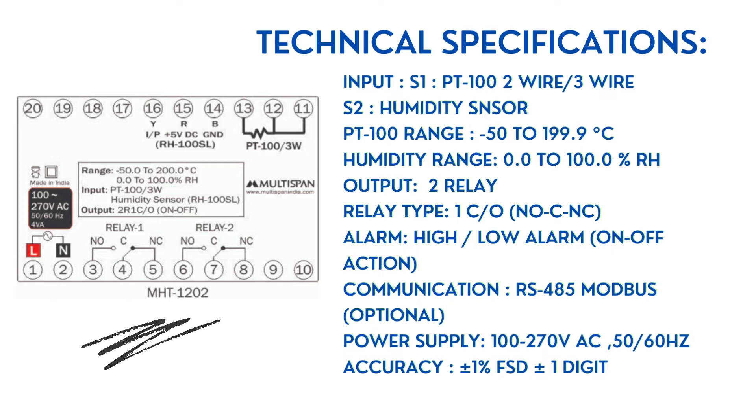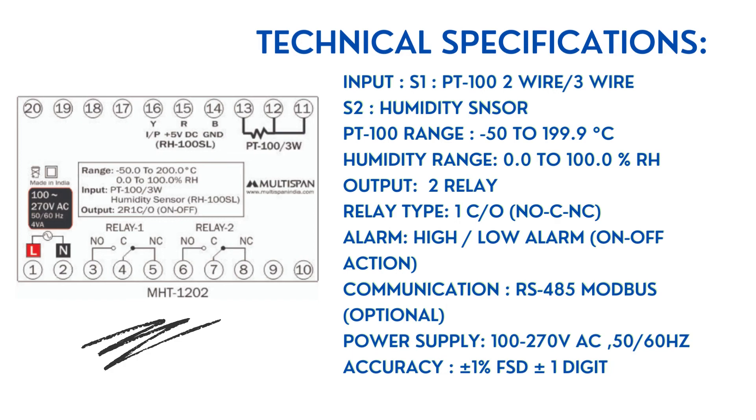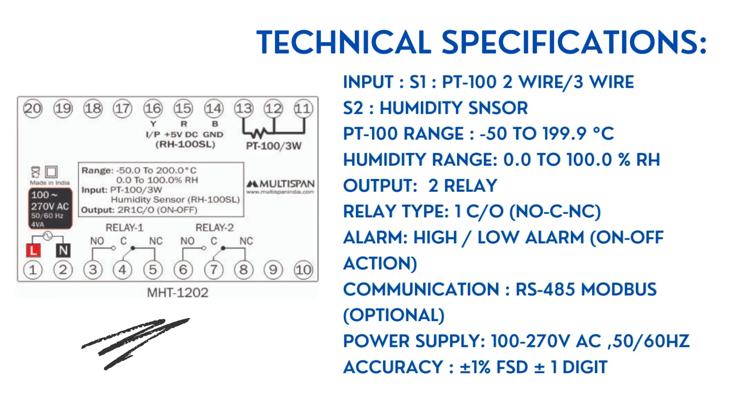Alarm is High/Low alarm, On-Off action. Communication is RS-485 Modbus, optional. Power supply is 100-270V AC, 50/60 Hz. Accuracy is ±1% FSD ±1 digit.